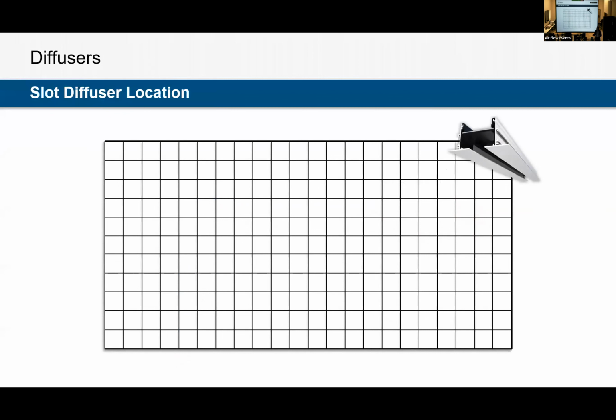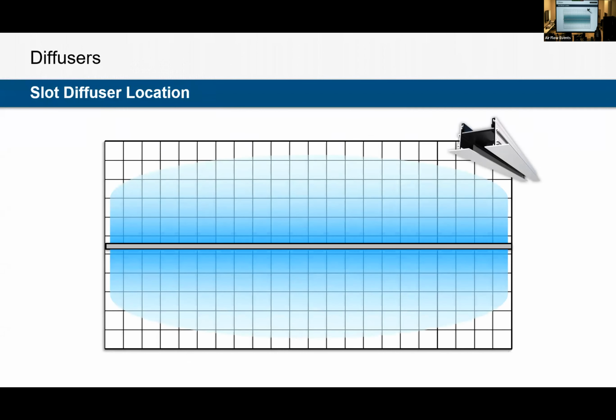Now this is a fun one. If we are designing a space with slot diffusers down the center of the room, they're going to discharge across the ceiling like this. What happens when we put our returns on the perimeter? Is it a good design or a bad design, and why?